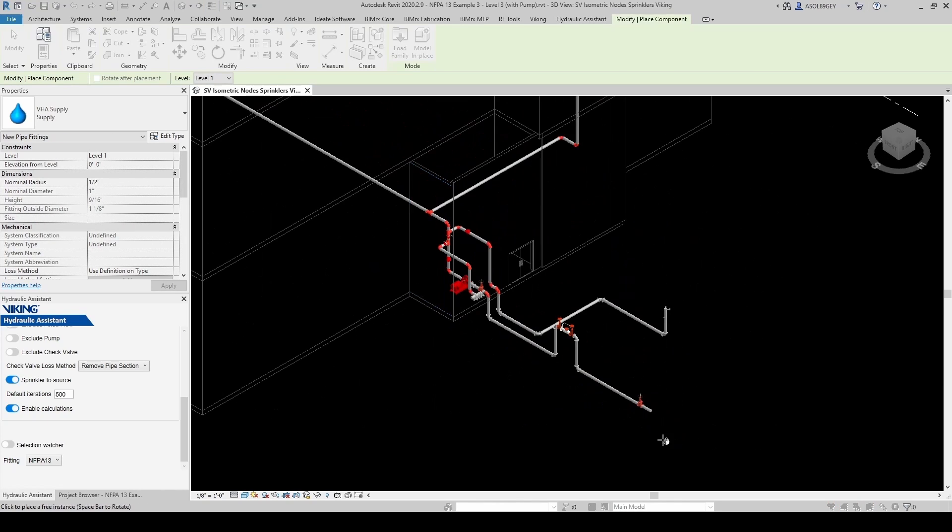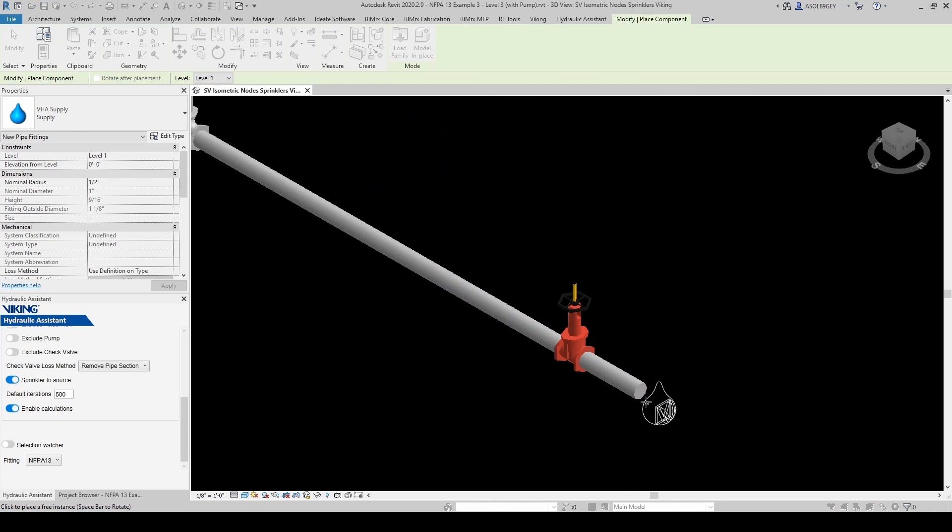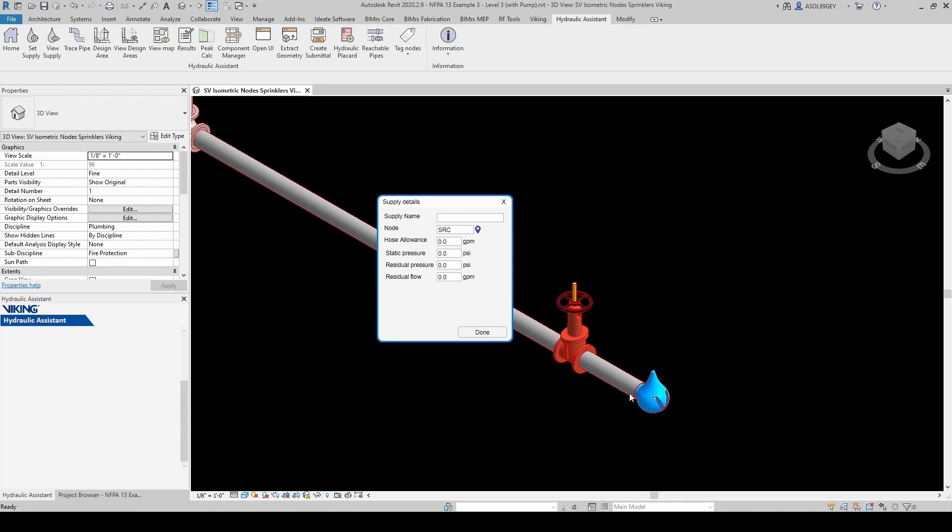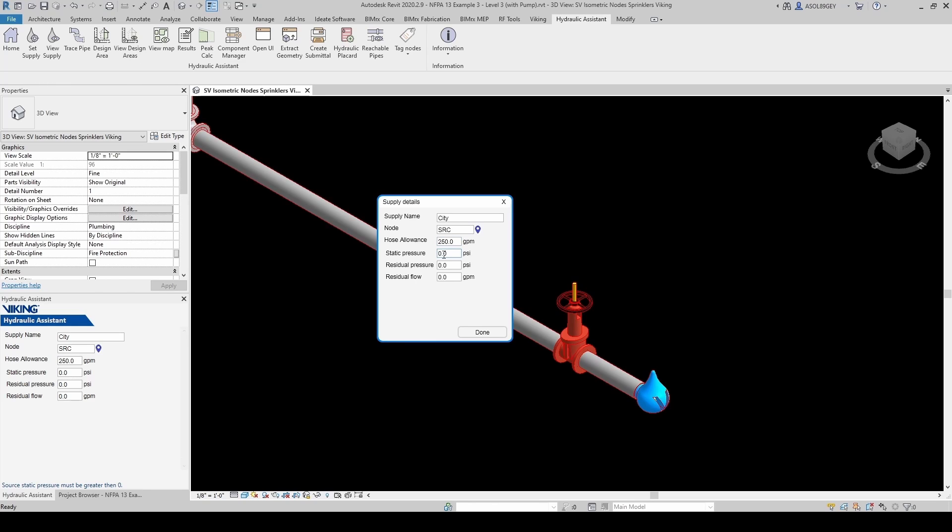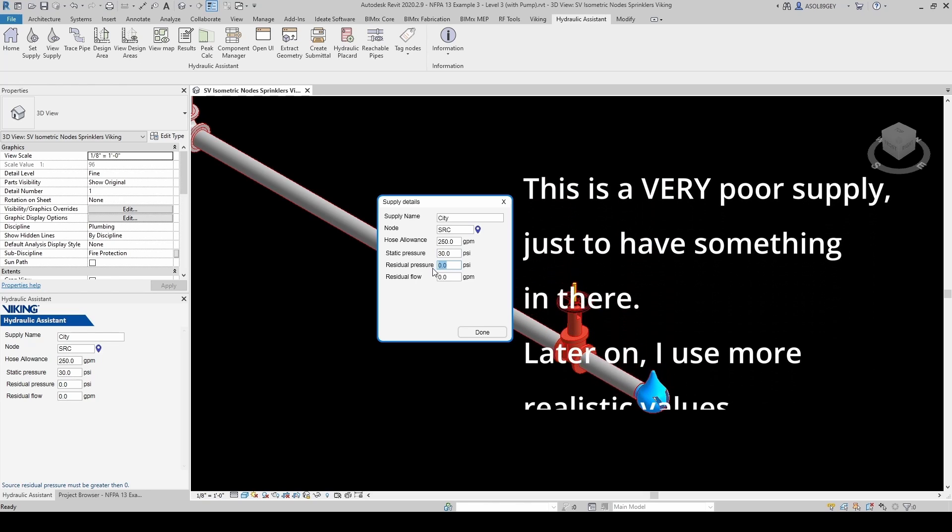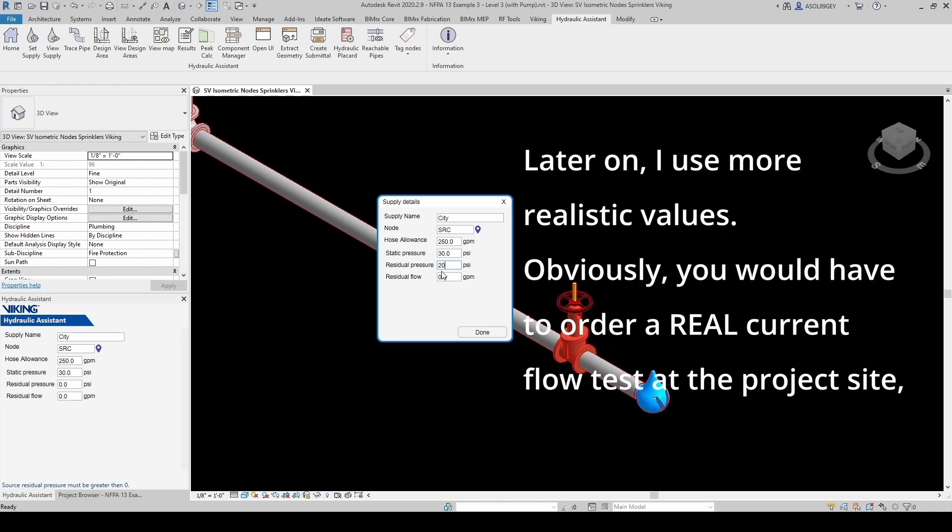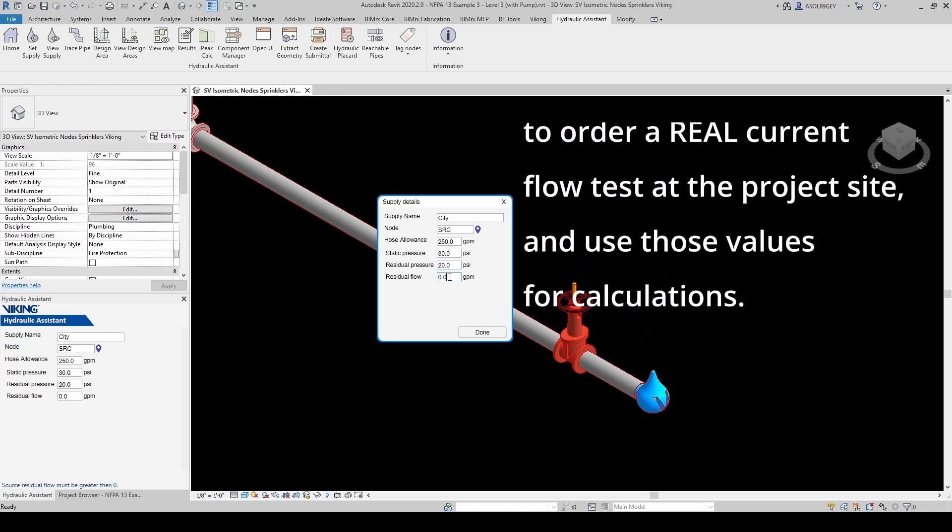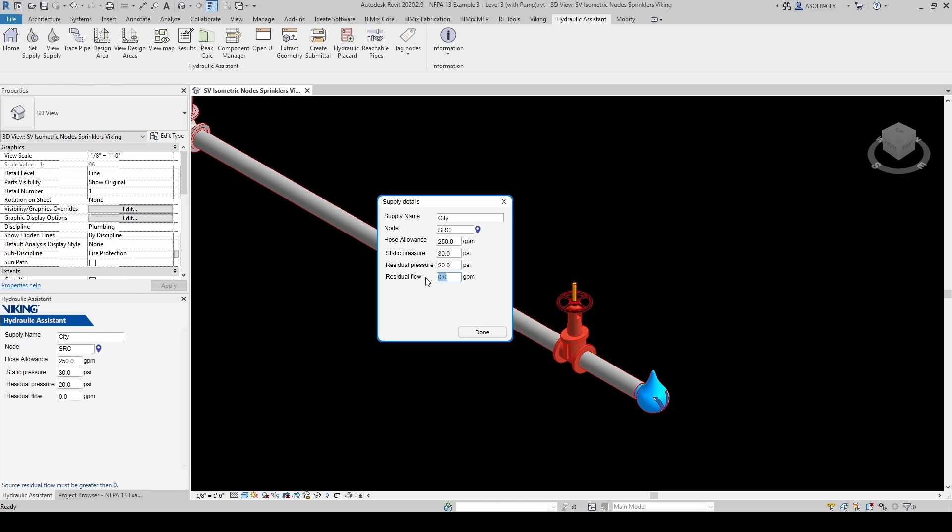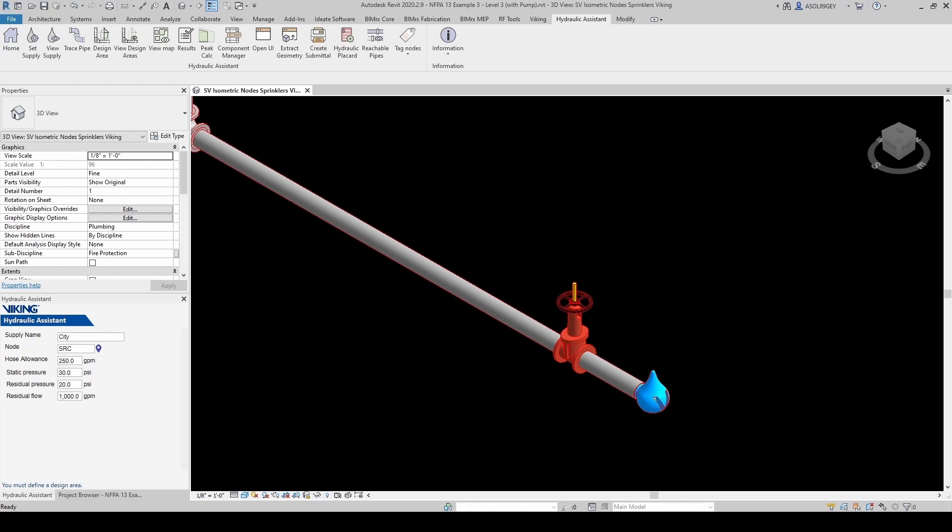And now you either select an element if you already have one, or you can insert one if you don't have one. So let's insert a supply. I'm going to place it right here. You'll see how my pipe highlights. And then for the supply name, I'm going to call this City. My node is Source. That's fine. For the hose allowance, I'm going to have 250 GPM for Ordinary Hazard. And I'm going to assume a very crappy supply. Let's say 30 PSI static, 20 PSI residual, let's say at 1,000 GPM.